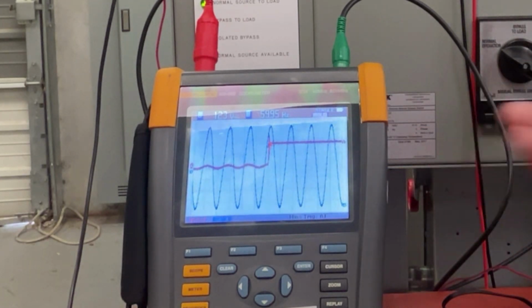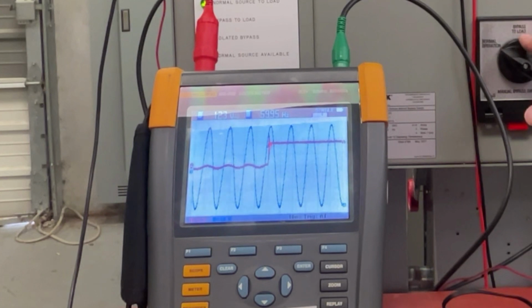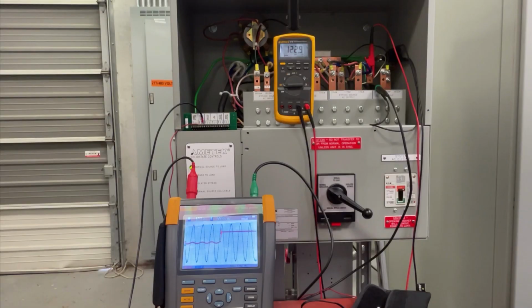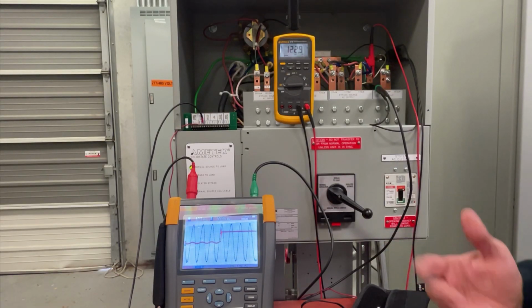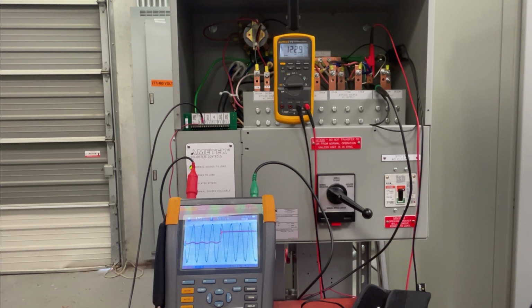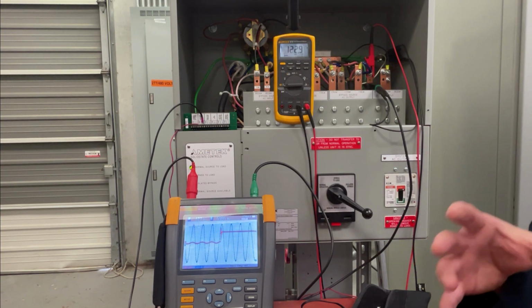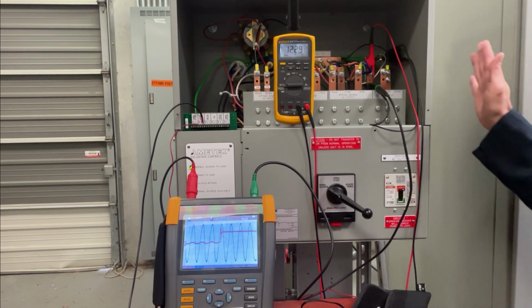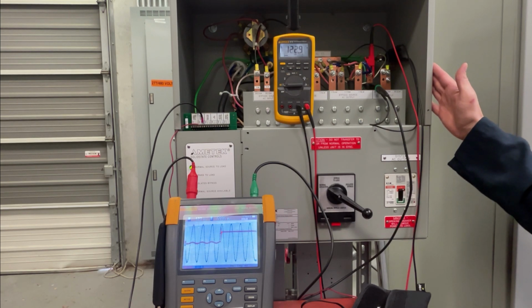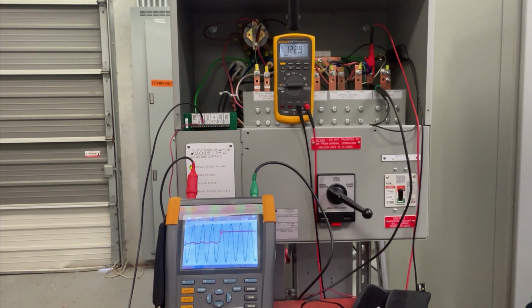So this proves that whenever you go between normal to bypass operation, there is absolutely no break in the output supply. It is a make before break transition inside this switch, and you should have no problems. So the RMBS is a really good addition, not only to AMETEK Solid-State Control UPSs if you only have an internal maintenance bypass switch, but any other UPS manufacturer that only has a maintenance bypass switch that is integral to the UPS itself. If you put one of these remote manual bypass switches on the outside of that, then it allows you to make your UPS completely volt free to do maintenance on it.